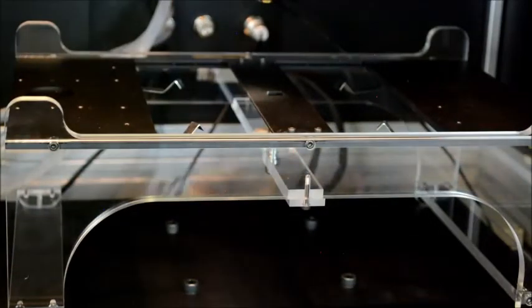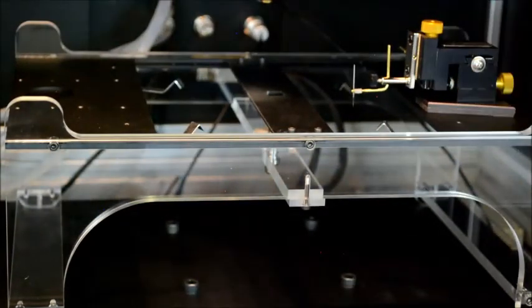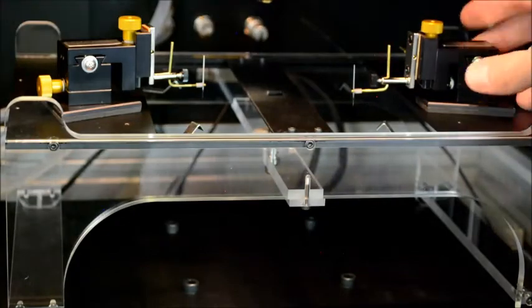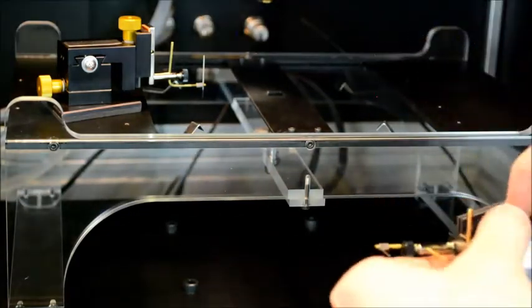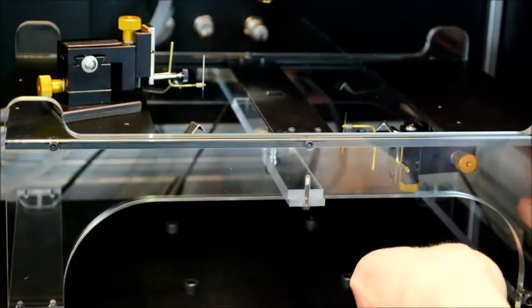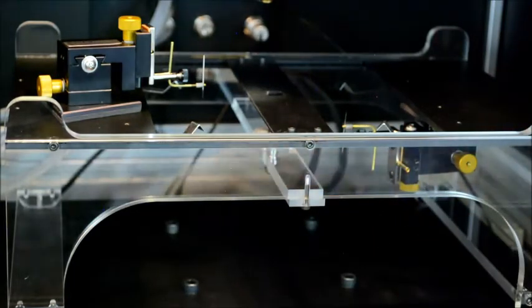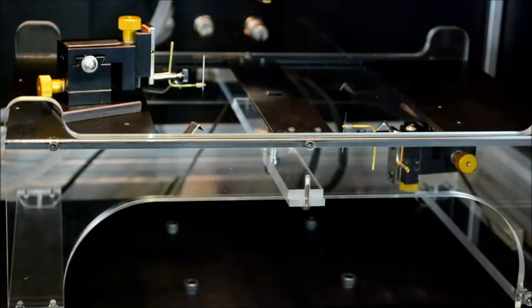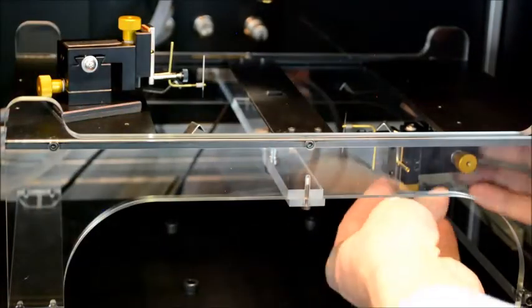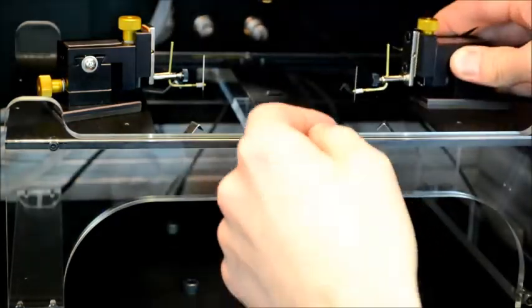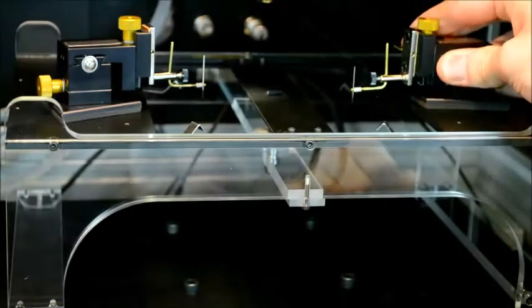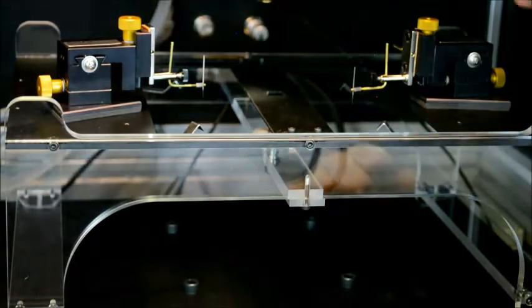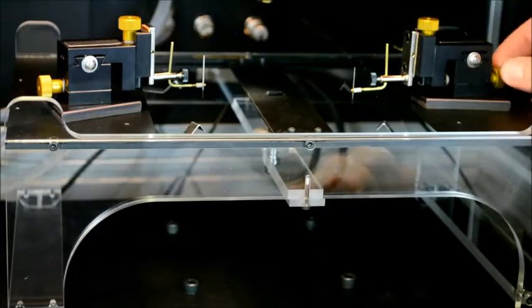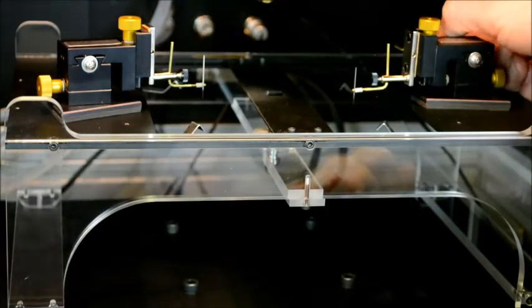The superstrate chuck is designed to be used with 2 different magnetic-based probes. These probes can be mounted from the upper face and equally from the lower face. In that manner, one can measure not only samples with 2 rear contacts, but samples with 1 front and 1 rear contact. Each probe is fitted with a needle contact, the height of which can be adjusted as required, and the probes also have X, Y, Z micro positioning facility.